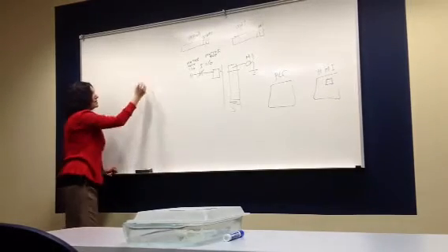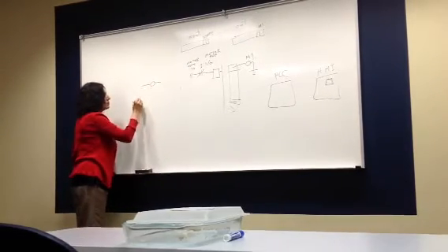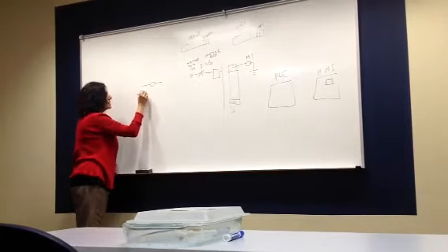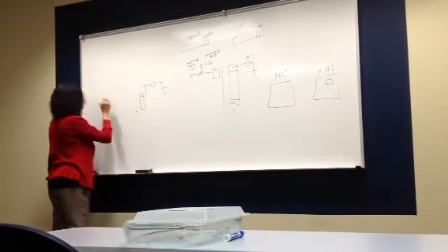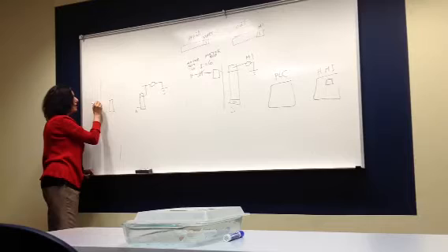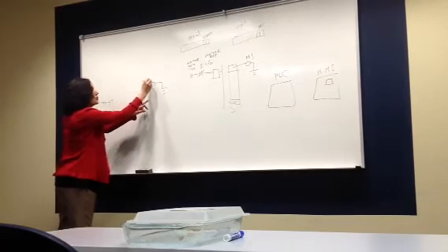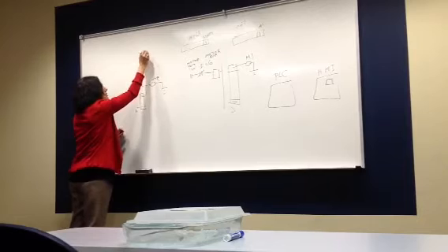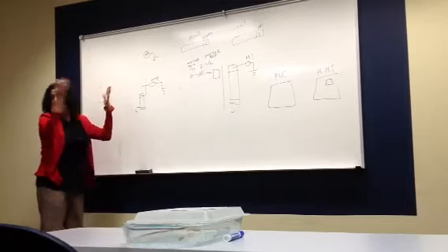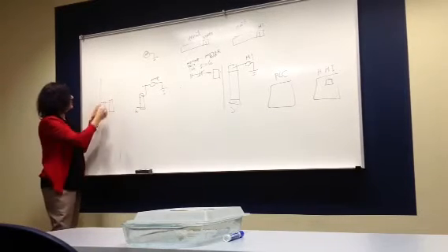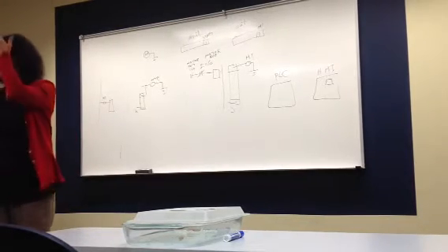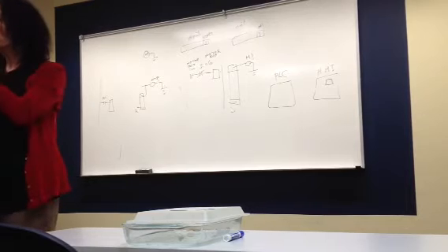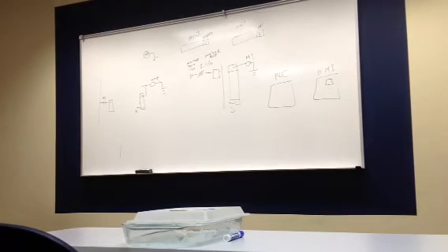We did send the motor output here, the output signal when we are in auto, and that's the hot. That's the output, you send it to the motor. And then on the same line, we receive the input, which is the magnetic side. That's the actual motor, MTR. Above that was the motor, right? Then we took the one phase and we had the magnetic starter. So the input here, M1, remember? You should have covered all of that previously. So the input is coming from the magnetic starter to tell you the motor is running.